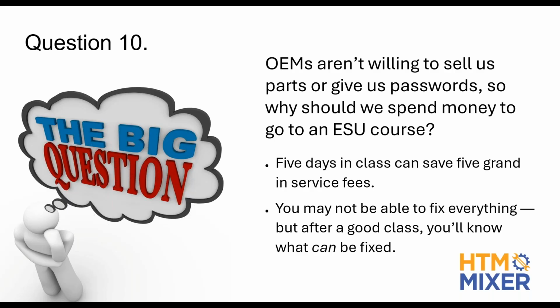back. I know that for sure because one of the biggest problems in the Force Triad, I know they're end of life now, but at the time, the biggest problem they were having is a 300 error. 300 error said the scanners aren't working correctly. And people would call me afterwards and said, I just sent this back to the OEM. And I said, oh, I wish you would have let me know this before you sent that back in. I could have saved you $5,800 because as soon as that goes back to Medtronic, they're going to change all of the scanners. They don't have to be changed.